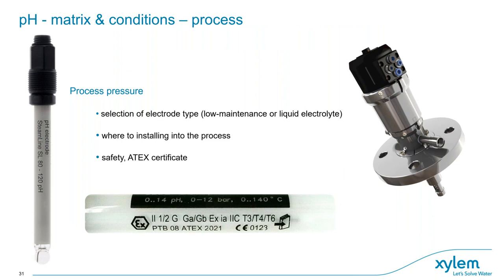For process pressure: when an electrode is installed in a process, the electrode type must be chosen carefully. It is easy to install a solid-electrolyte electrode, but liquid-electrolyte electrodes require more effort. Do not install the electrode directly near a pump, as the pressure may change constantly and significantly reduce electrode lifetime. Also consider safety requirements — an ATEX certificate may be required.